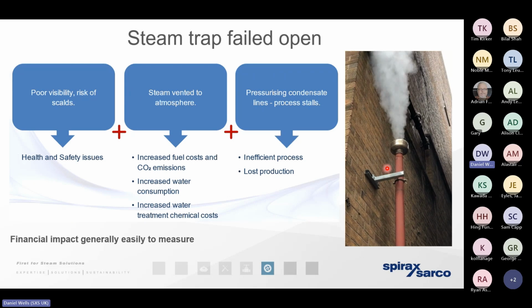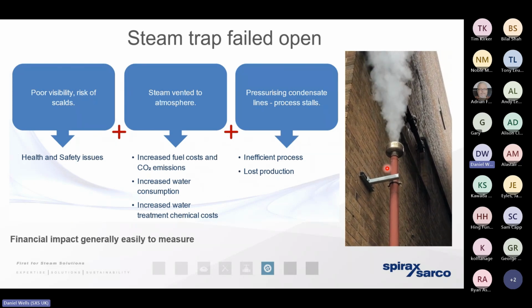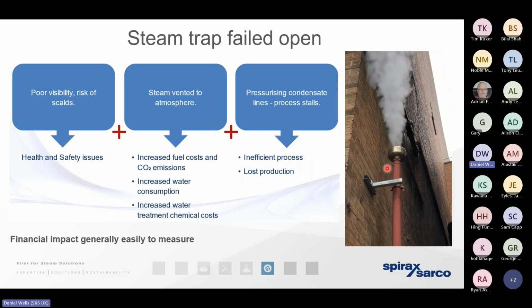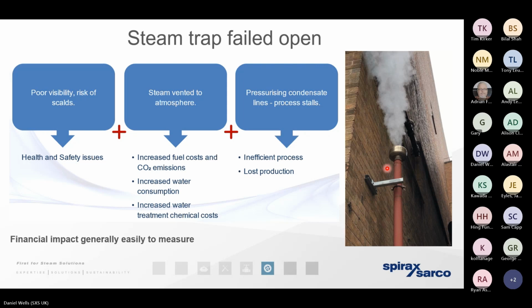The problem is, and it doesn't matter what type of steam trap we're talking about or where it's located, steam traps are mechanical devices and they can and they will fail, especially if it's the wrong type of steam trap selected, if it's been sized incorrectly, installed incorrectly, or if it's failed to be maintained. Another rule of thumb, we'd probably expect a 1 in 10 failure rate. And that assumes that we've got a good quality of steam and that the steam trap has been engineered correctly. So if our client had 100 steam traps on site, we'd expect 10 of them to be in the failed position at any one time.